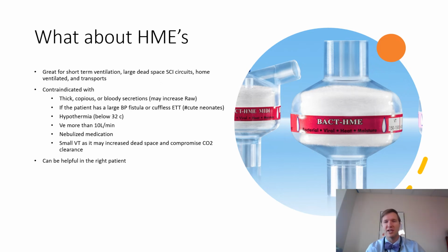When these patients first come in, it's a good way to make sure they get adequate humidity starting right away. They don't have to wait for a heater to warm up or anything like that. So they're great for short-term ventilation. Some places use them longer than short-term, and we'll talk about that in a second here. There are some issues here.